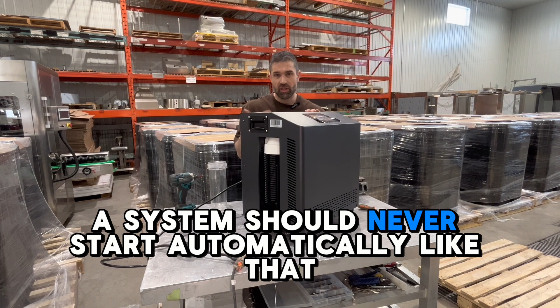That makes no sense. A system should never start automatically like that. You should be able to set your parameters first on the screen. Right now the pump runs dry, which can burn it out very quickly. There's no protection system in place. That's a huge flaw, you should have a start-stop on the touchscreen.